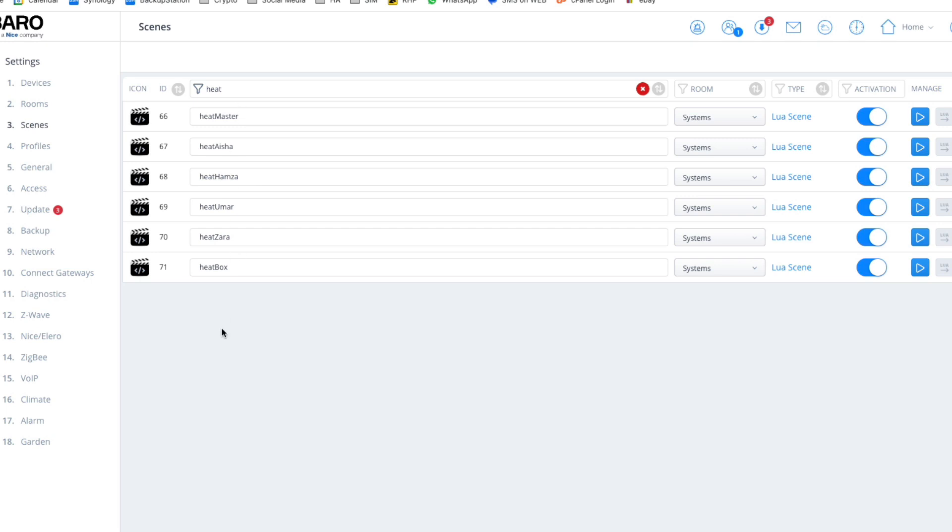So literally, all these do is each zone has a scene attached to it. All they do is measure the temperature using my motion sensors, check it against the climate panel to see what temperature I want. And if the temperature is below what the climate panel says, it then opens up the TRVs and turns on the boiler, and therefore I have heat in that particular room. Any other room will not get heat because the valves are going to be closed.